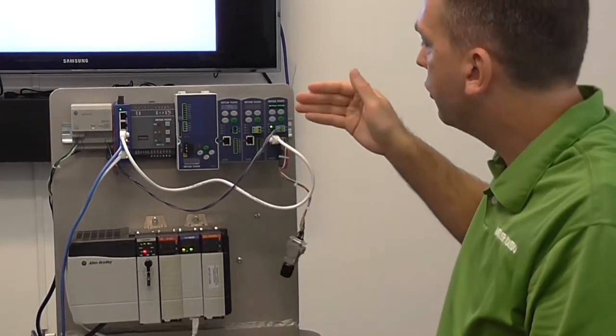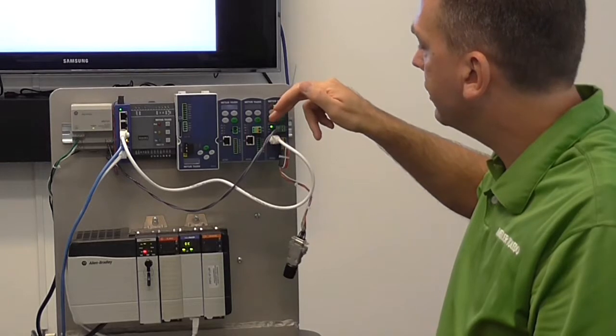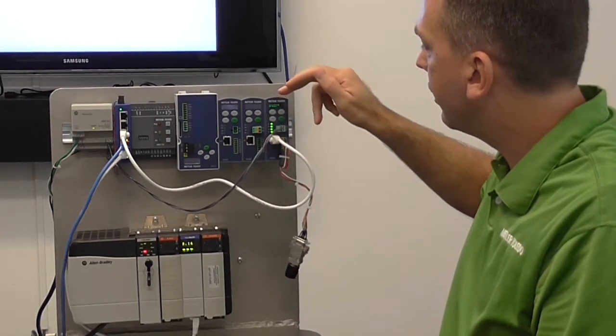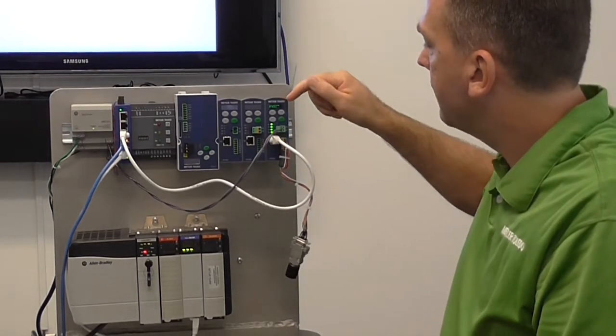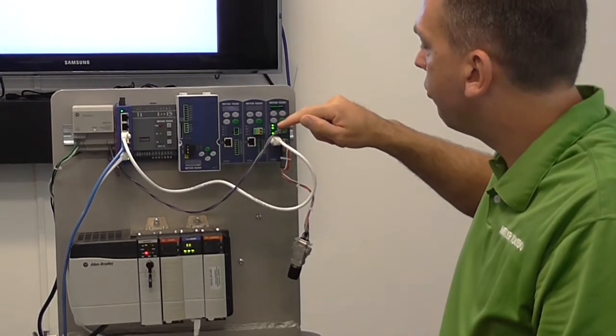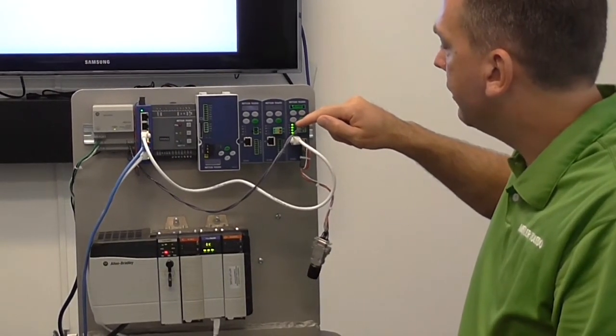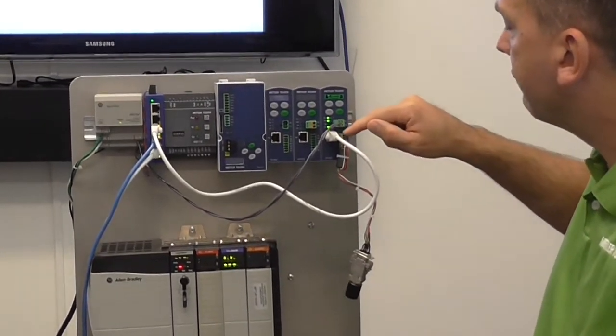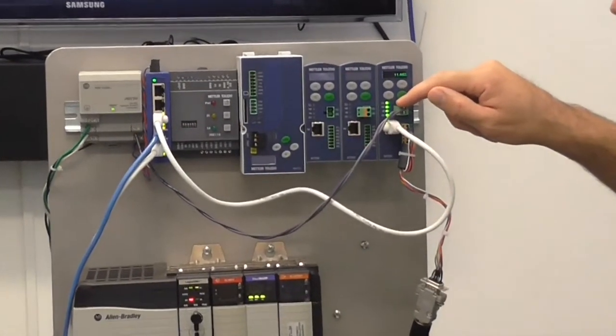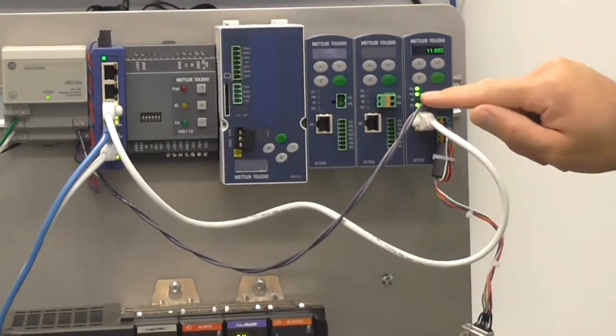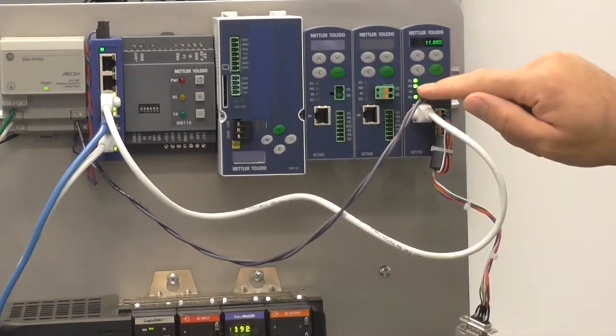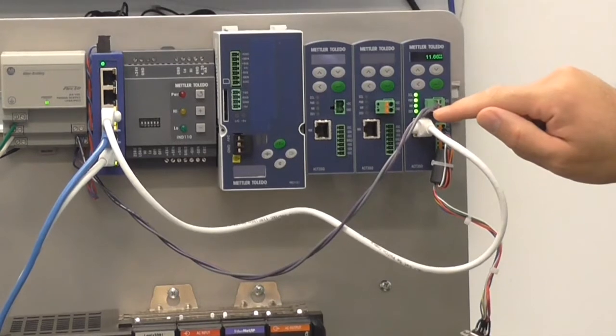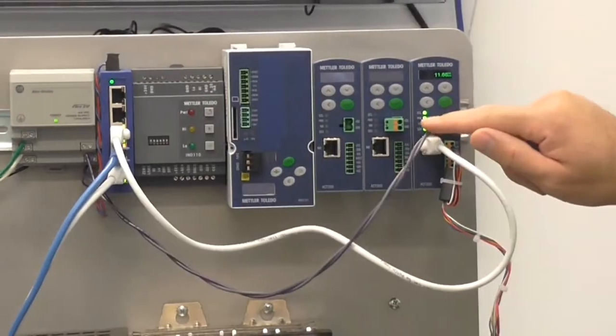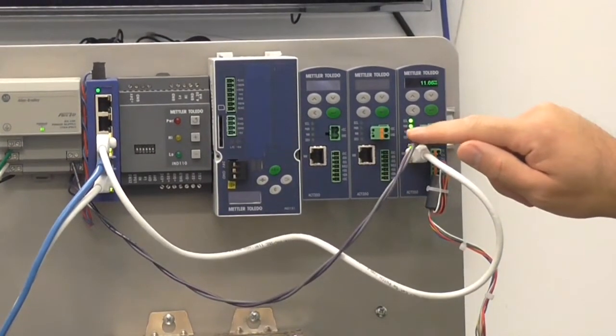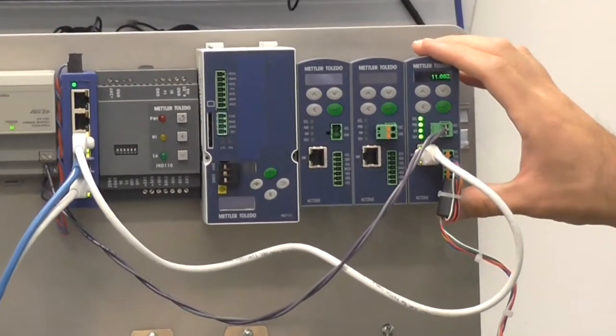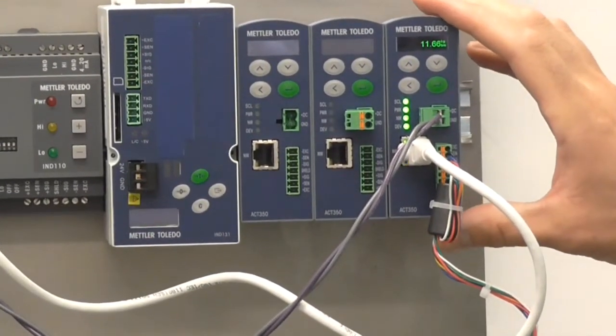So now it's going to go through a boot up process. We'll see that the LEDs are going to light up as it initializes. When it's done initializing, all four LEDs should be solid. The first one is for the scale, verifying you have a valid connection. Power is obviously that we have power to the unit. The network connection will go solid green here momentarily, indicating we have a good connection to the PLC. And then finally we have the device LED, which is verifying that the unit is in proper operating status.